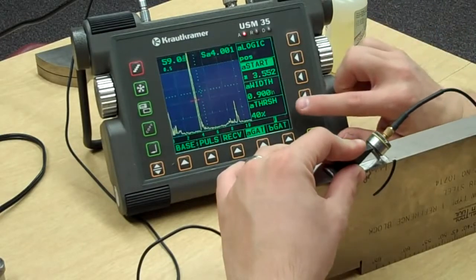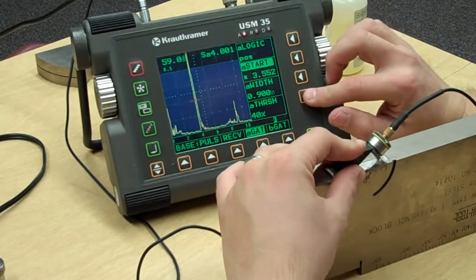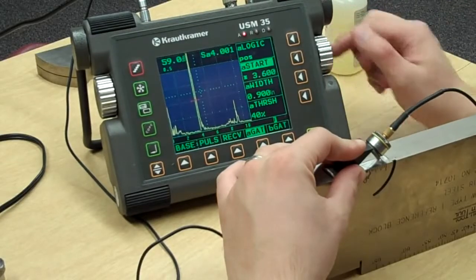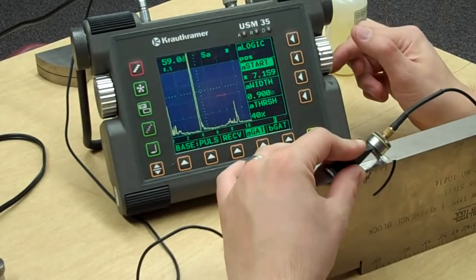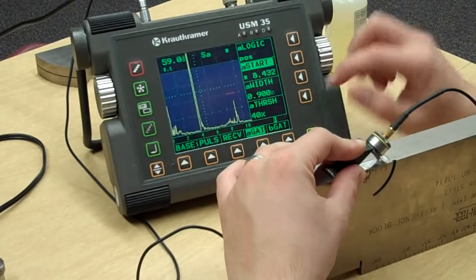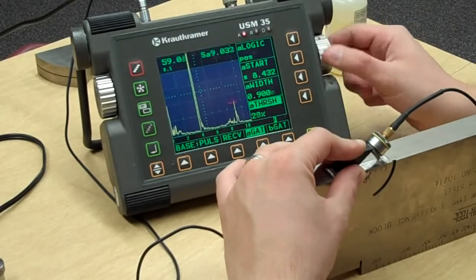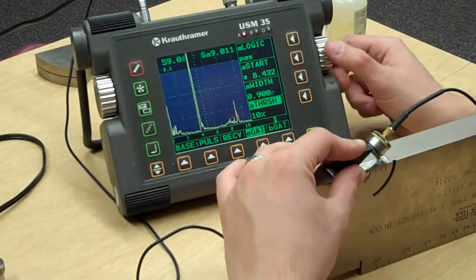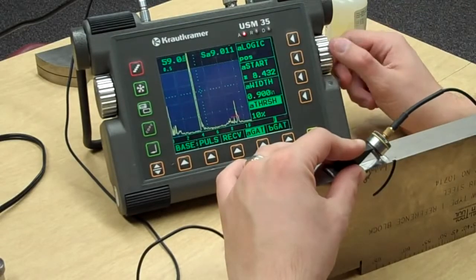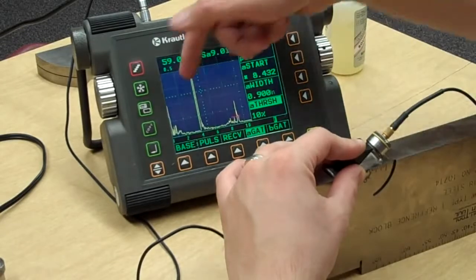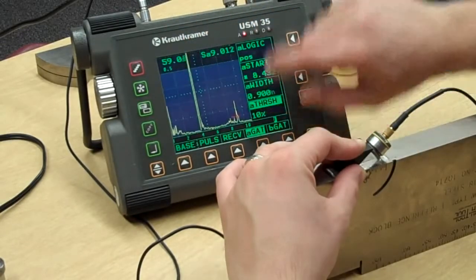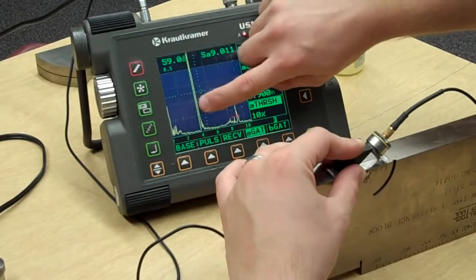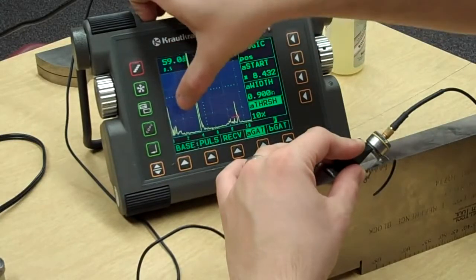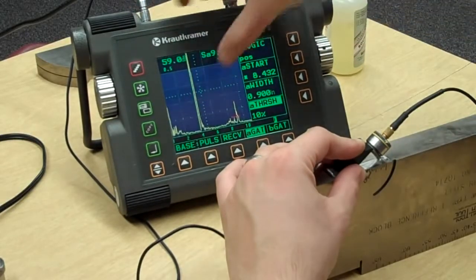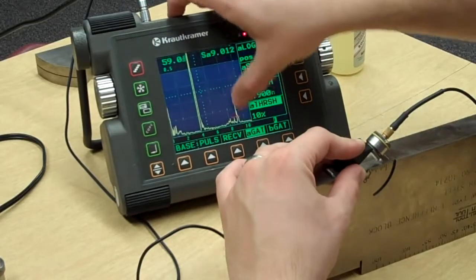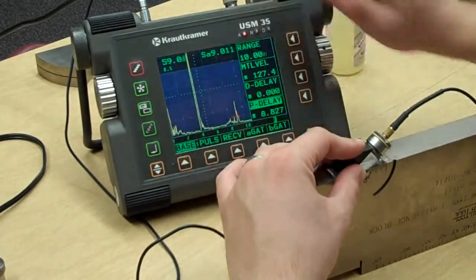And then I'm going to take my gate again and move it over here over the other signal. But since it's not up to 40%, I'm going to drag it down a little bit, and it's going to tell me I'm right at 9.011. Okay? Which means I'm pretty close to 4 and 9, which I can see on my screen here, and you can see too that I have a signal over here. Here's 10, 20, 30, 40, so there's 4 inches on a 10-inch range. 50, 60, 70, 80, 90%, there's 9 inches on a 10-inch range.